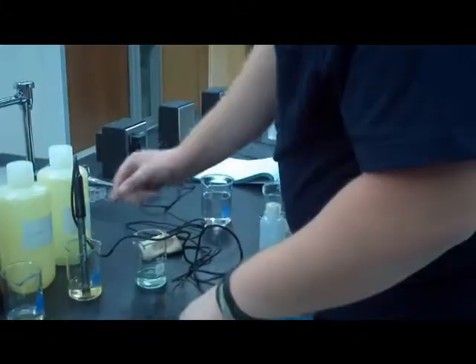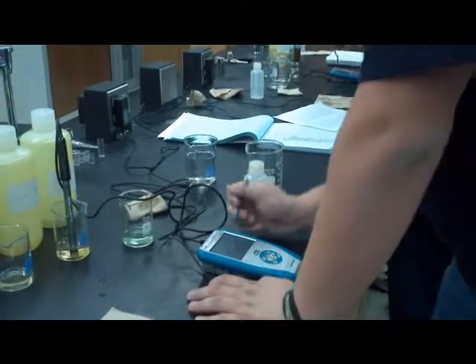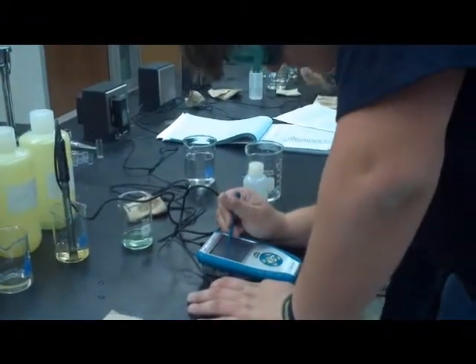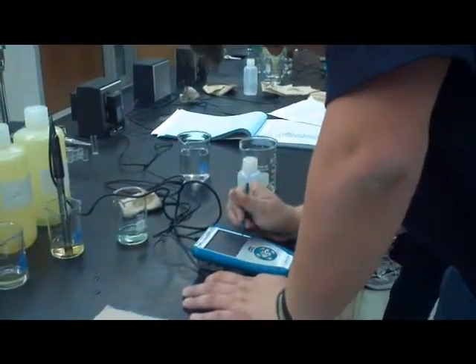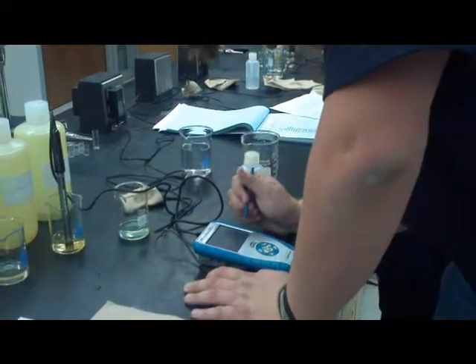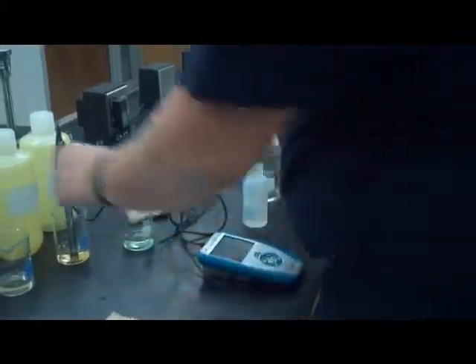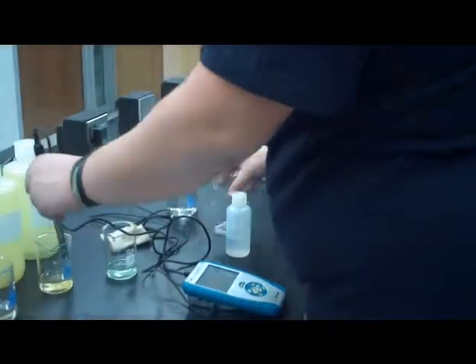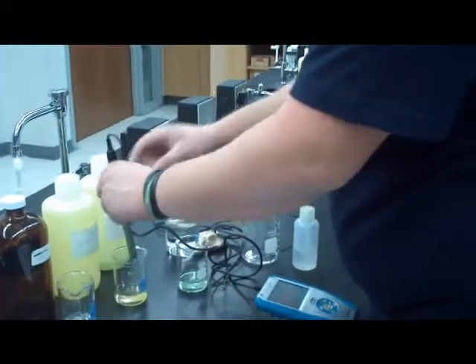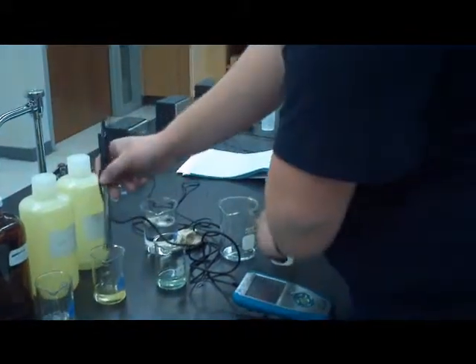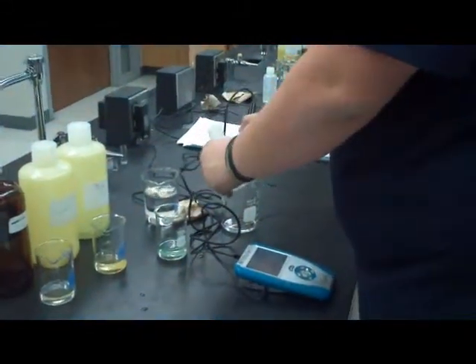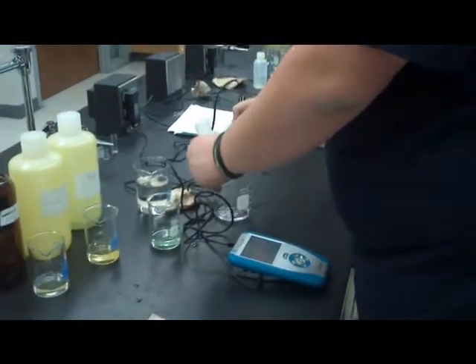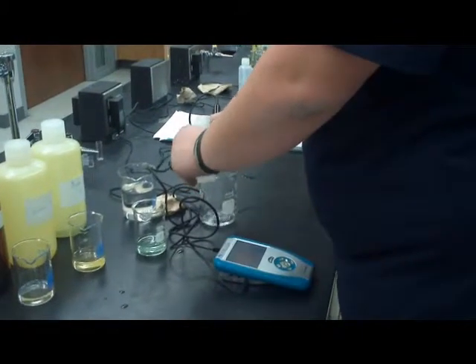Once the voltage reading has balanced, the key needs to be hit under the second data value. Now the probe is removed from the buffer solution and rinsed. Then it is placed back into the holding solution.